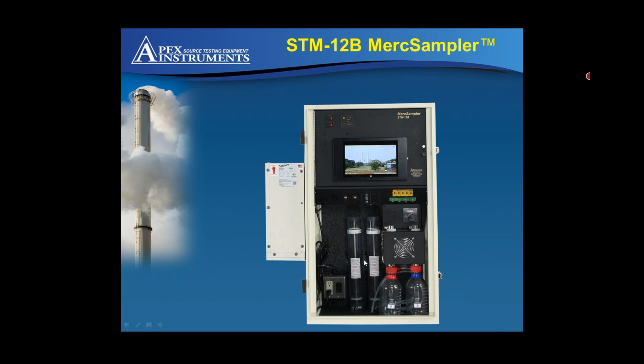There's a combination of a couple of different things in here: carbon, Purafil, silica gel that periodically need to be changed out as they get used up. Our bottles here collect the moisture knockout and need to be emptied periodically, and that can be done when you go up onto the stack to change out your traps. Right now, and I'm not sure how familiar you guys are with the reporting and the legislation, but part of the PS12B is needing to report stack gas moisture, say Method 4 on a traditional US EPA Method 4.